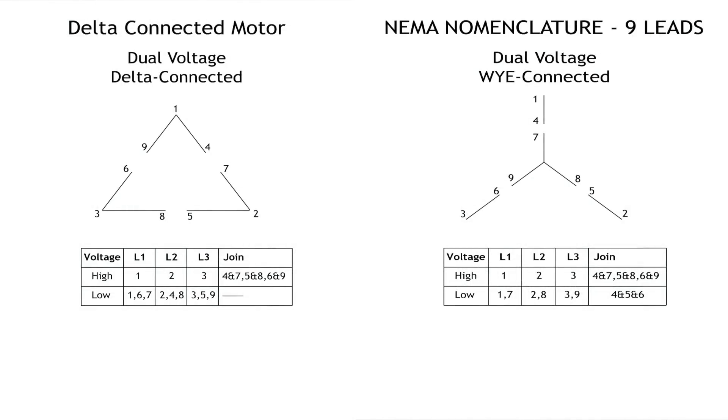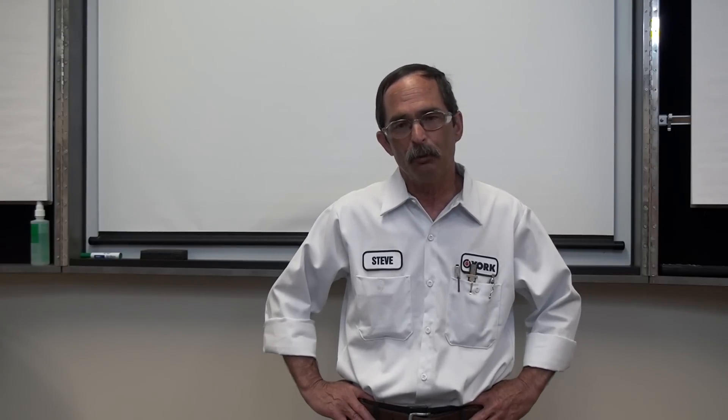If we're missing a number on one of our leads, by looking at the actual configuration and checking for continuity we can have a good idea which number is missing. If say one and four have continuity, and you've got a one but you're missing number four, then we know that the lead with continuity with number one is number four. If you're missing both numbers in the same phase, then we've got to do this completely differently.